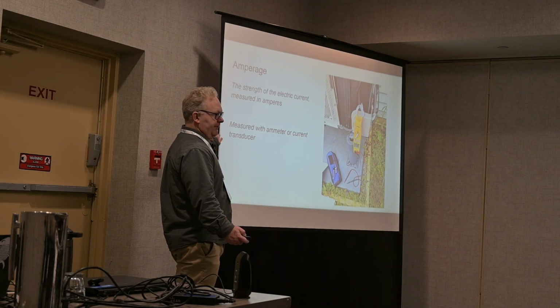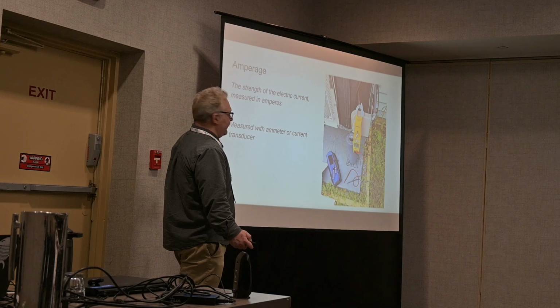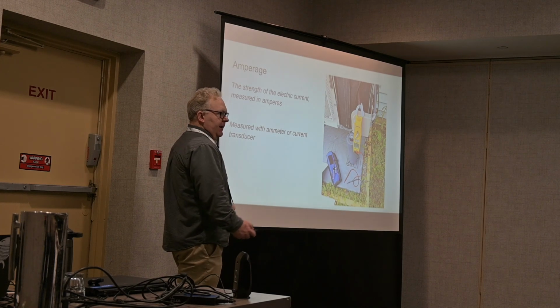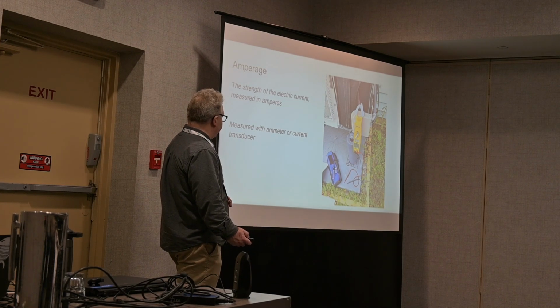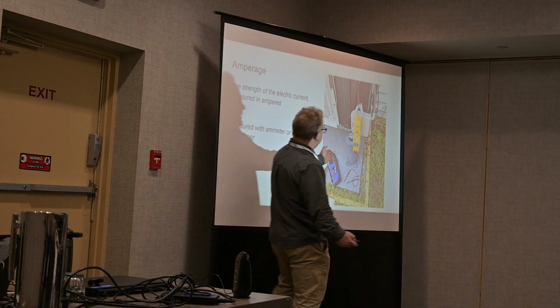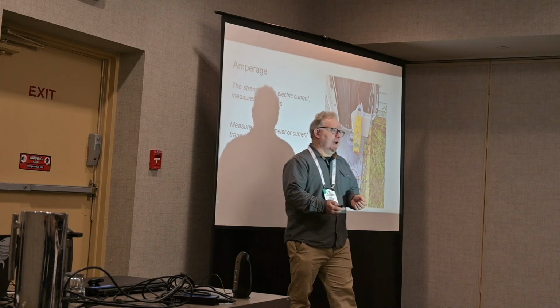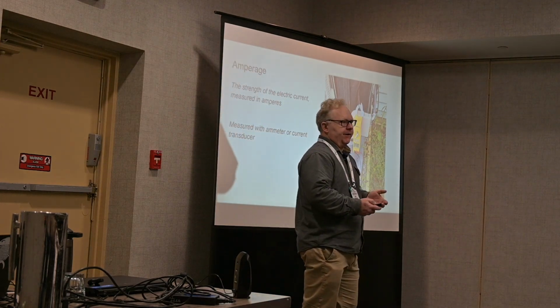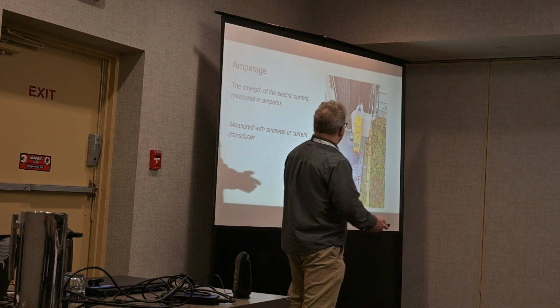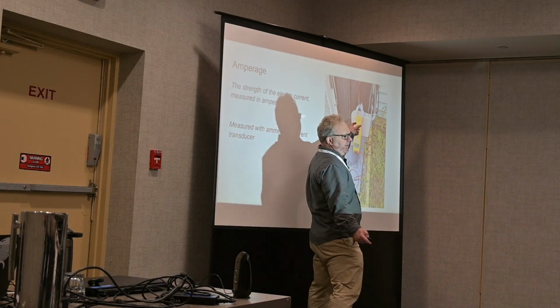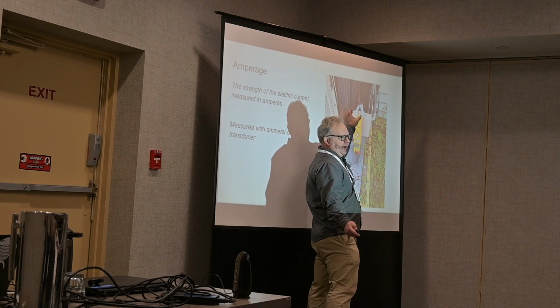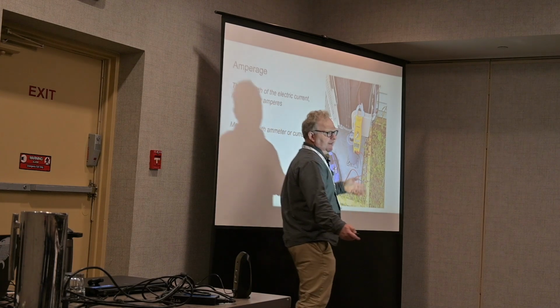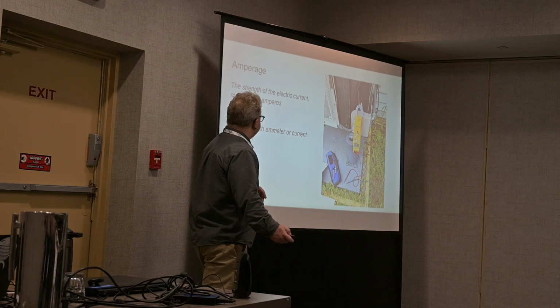Amperage is the strength of the electrical current. It's how many electrons are flowing through that conductor at any moment in time. And it can be measured with a clamp-on ammeter like I've shown here. When we do circuit monitoring in homes, for example, with an Emporia monitor or something like that, we're using similar clamp-on devices that clamp around our conductors, sense the fluctuating magnetic fields, and translate that into a measurement of current.